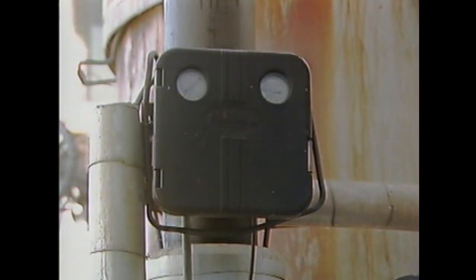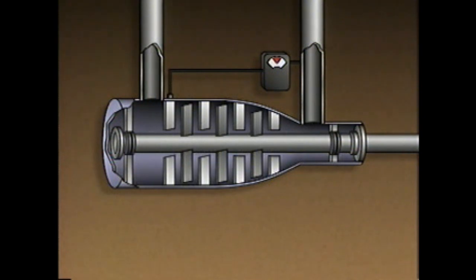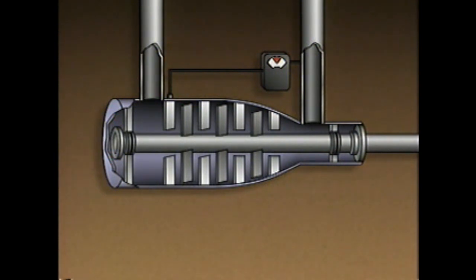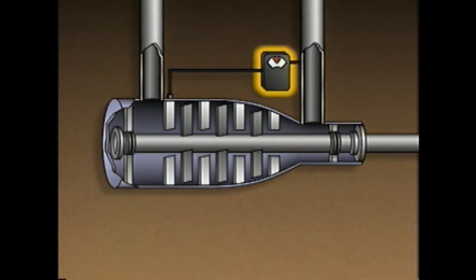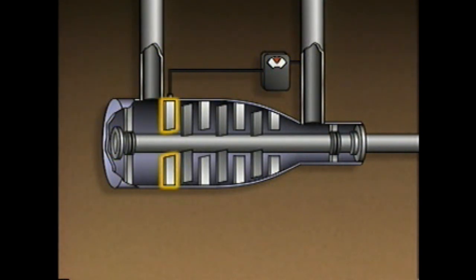Compressor instrumentation and control devices also maintain the gas discharge pressure. For example, this simplified illustration shows an axial compressor with one type of control system that maintains a constant discharge pressure. The main components of this control system are a pressure controller and inlet guide vanes.